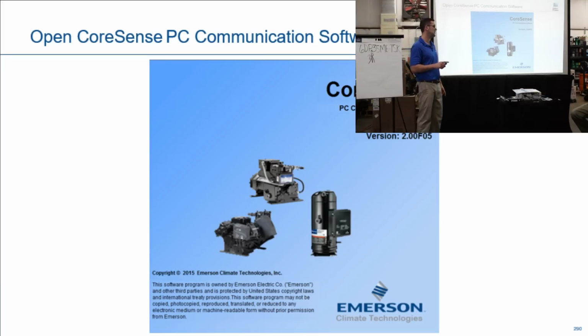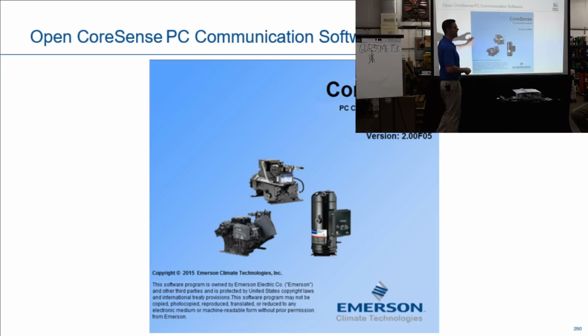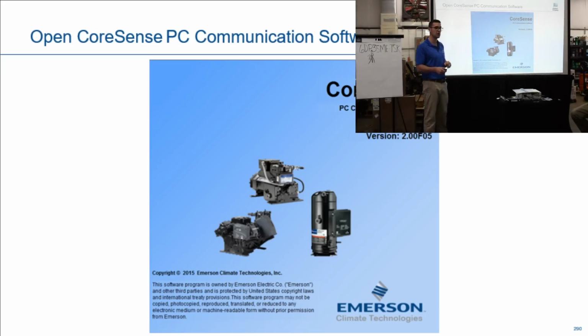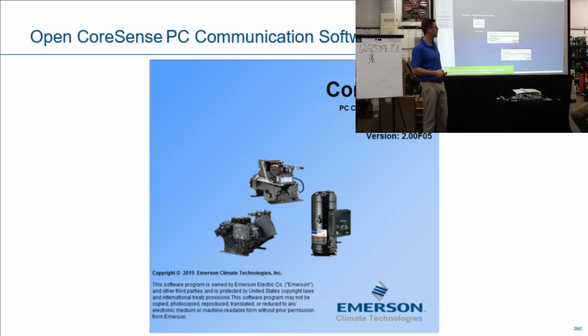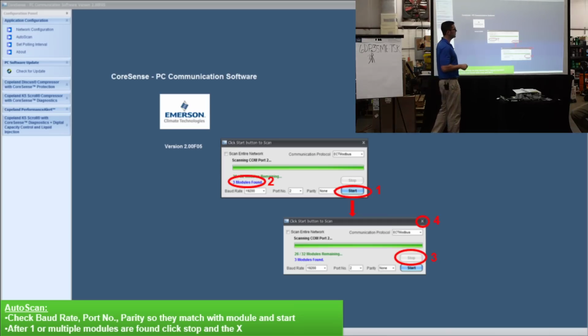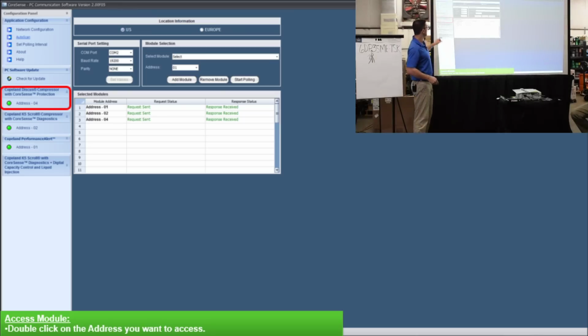Accessing the information. This is super important. So here you hook your computer up to the CoreSense module, you load the program up, and this is what you need to do. You just press start. Okay, as long as it's wired up properly and your dip switches are right, but you look in your AE Bulletins, you press start, all of a sudden 3 modules found. You stop that and you close it out. And then what you're going to see is them communicating with 3 different devices. And as you can see, we're response received.